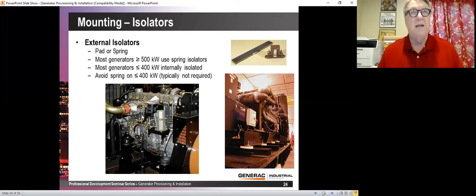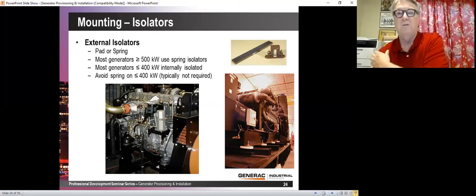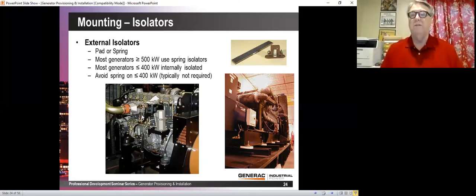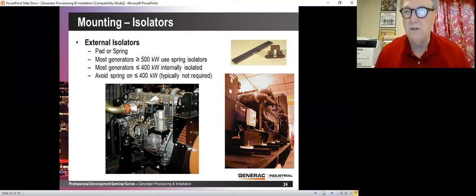And now the tank, instead of having a nice flat surface, is sitting on these springs. And not only does that weaken the tank and increase the likelihood of cracks in the tank, but it actually can create problems in a seismic event. The isolation for all generator manufacturers now is very sophisticated, and generally these generators are tested on a shaker table to assure that isolation is proper and that it's not enhancing and exacerbating the seismic events. If you go put springs under the tank, you're just going to mess that all up.